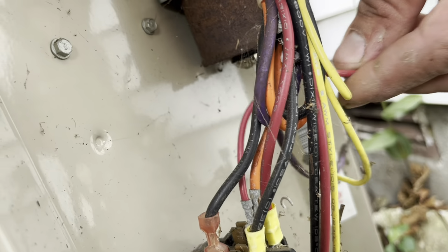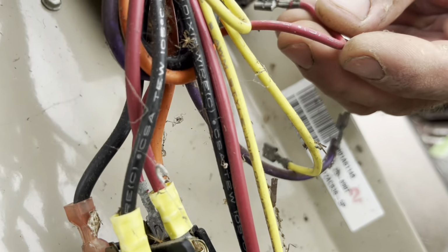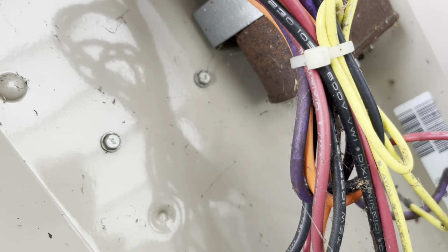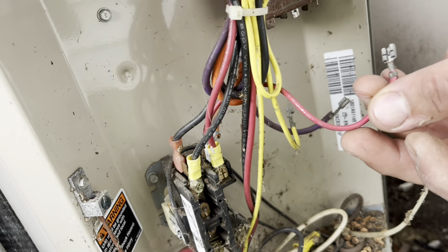Now the way I'm gonna check this - I was watching Misfits of HVAC the other night, and they were saying don't assume everyone knows what you're doing, film it. So I'm taking my common, which is coming off my capacitor. There's 3 wires off, right? Taking my common off the top of my capacitor - that goes to my contactor. That's gonna be my common to my capacitor.